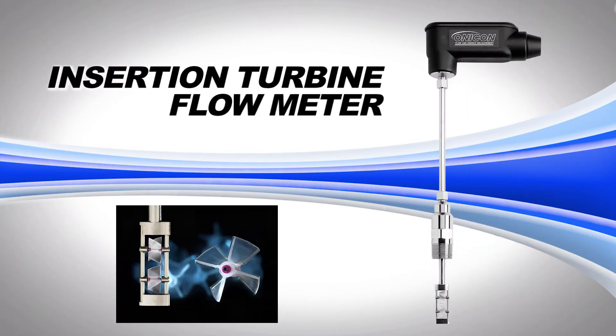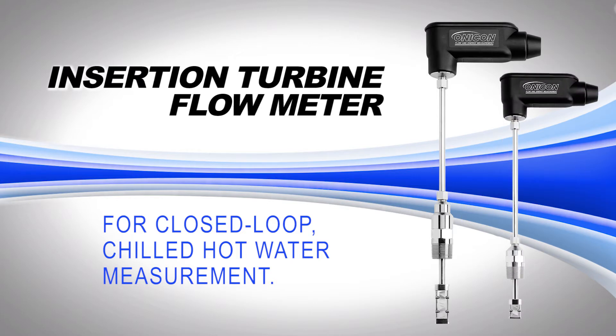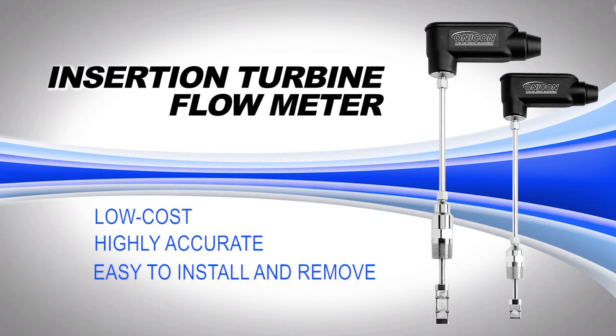ONICON's initial product was the popular insertion turbine flow meter for closed loop, chilled, and hot water measurement. Both the single and dual turbine models are low cost, highly accurate measurement devices that are easy to install and remove from the system without shutting down the line, and each meter is individually wet calibrated specifically for your application.